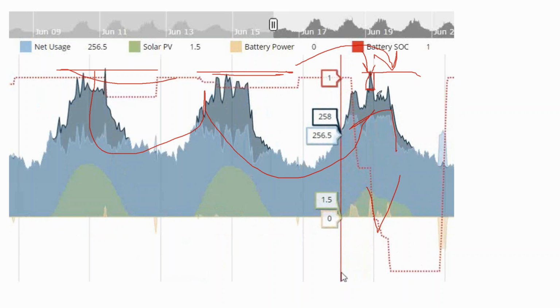What is the maximum 15 minutes for the entire month? It's not that solar doesn't produce demand electricity at demand times, and it's not that we can't rely on solar to reduce facility demand on a sunny day. It's that on a partly cloudy day, one 15-minute window out of the entire month, that one cloud sits on top of our solar array, turns it off, and our facility demand spikes through the roof. We see no demand savings even though 95% of the time our array is reducing our demand charge, because we have to control demand 100% of the time.